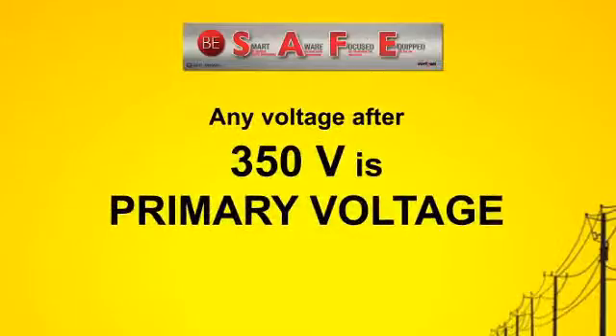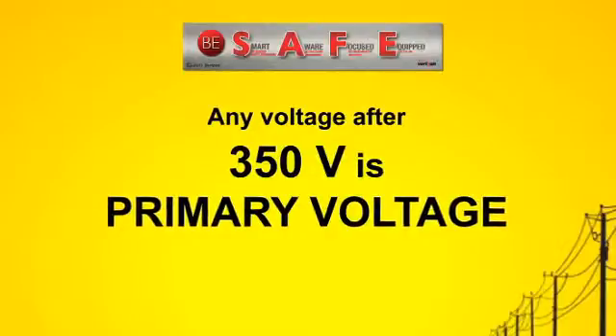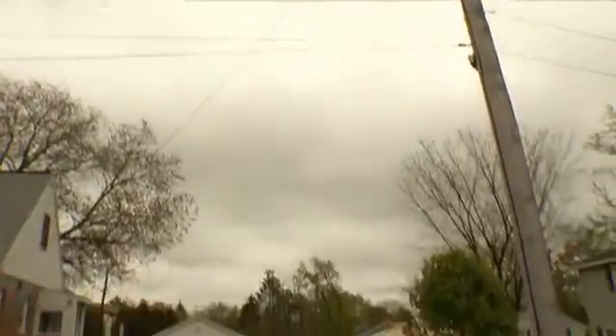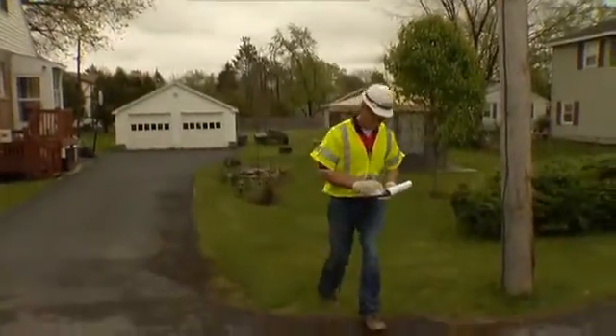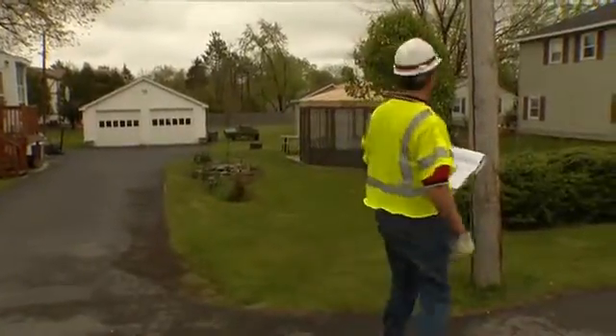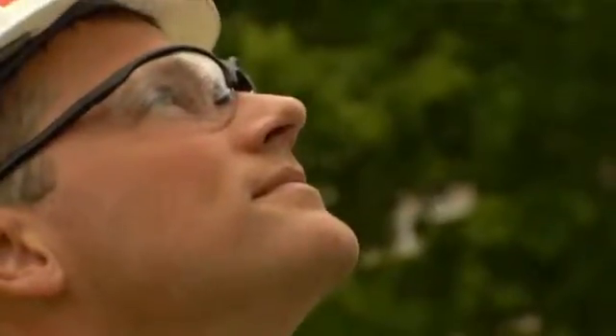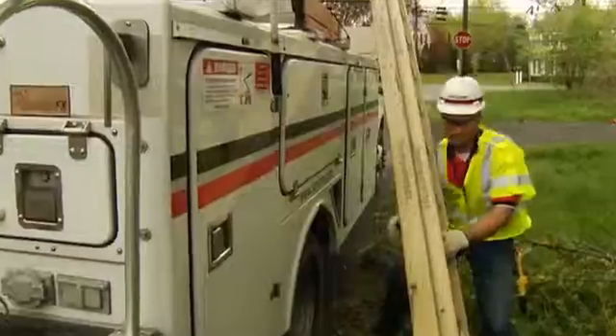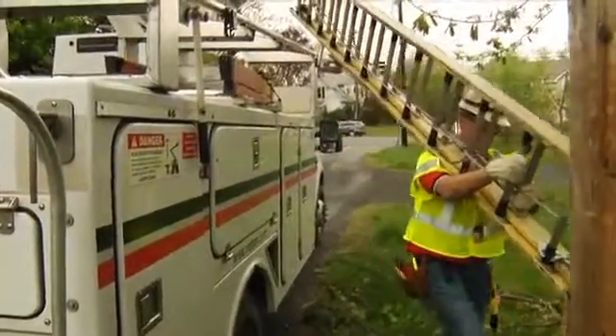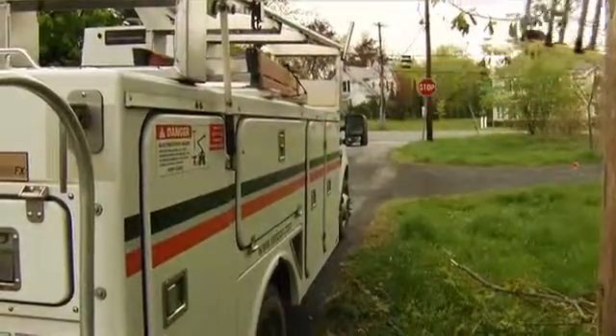The bottom line in all this, what you should remember, is that after 350 volts, it's called primary voltage. And if you're not sure what you're dealing with, if it doesn't say it clearly on your work print, consider whatever you are dealing with to be the maximum voltage and maintain the maximum approach distance. And don't forget to include any tool or piece of equipment you are in contact with in your calculation. If these approach distances cannot be maintained during your work operation, do not proceed and notify your supervisor immediately.